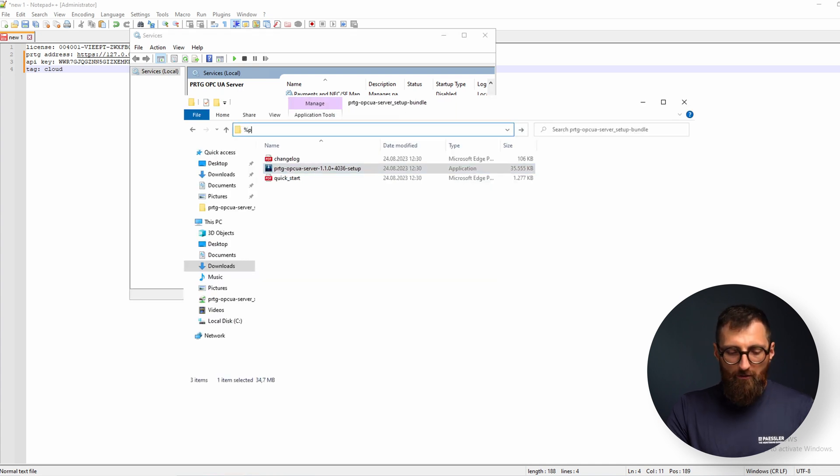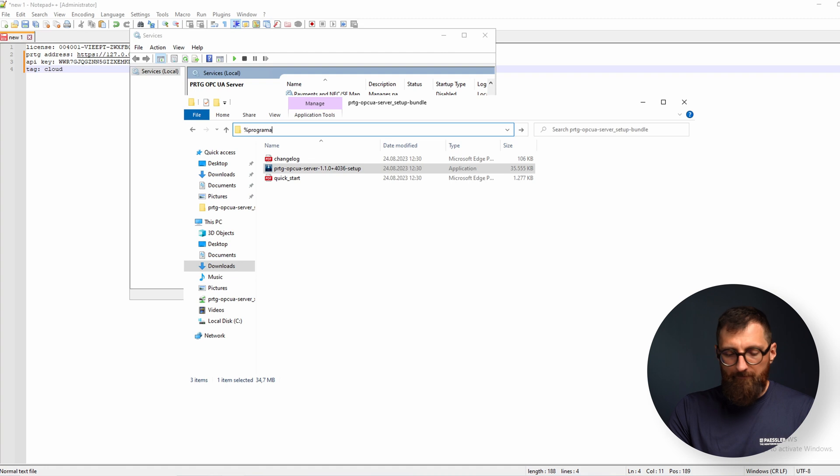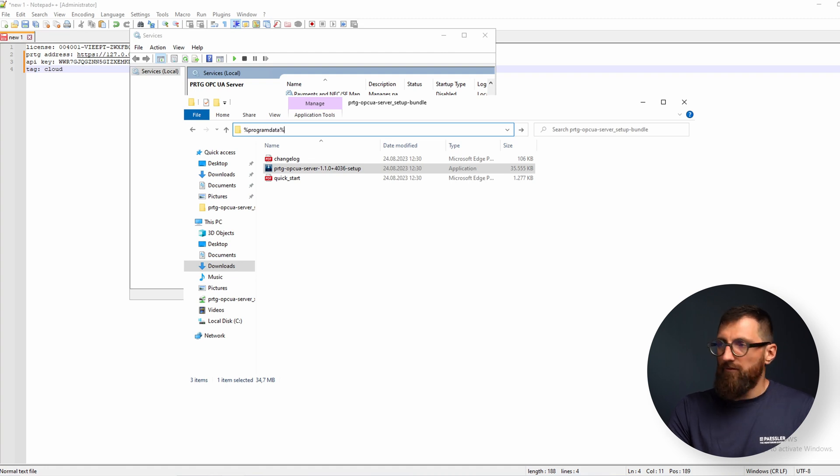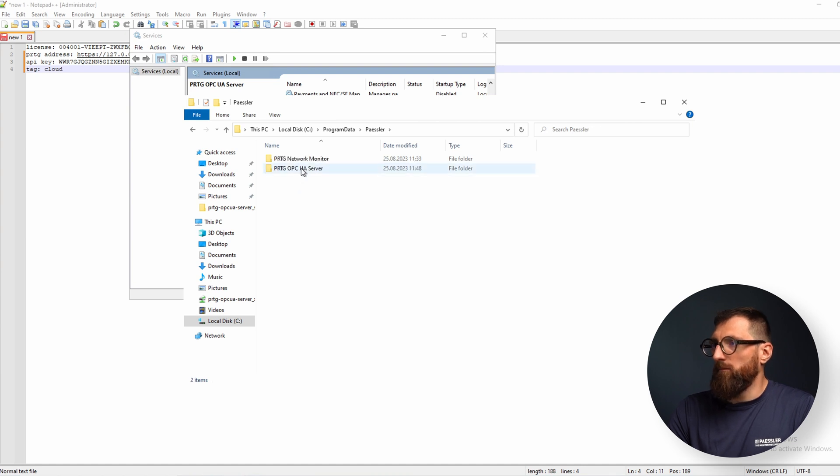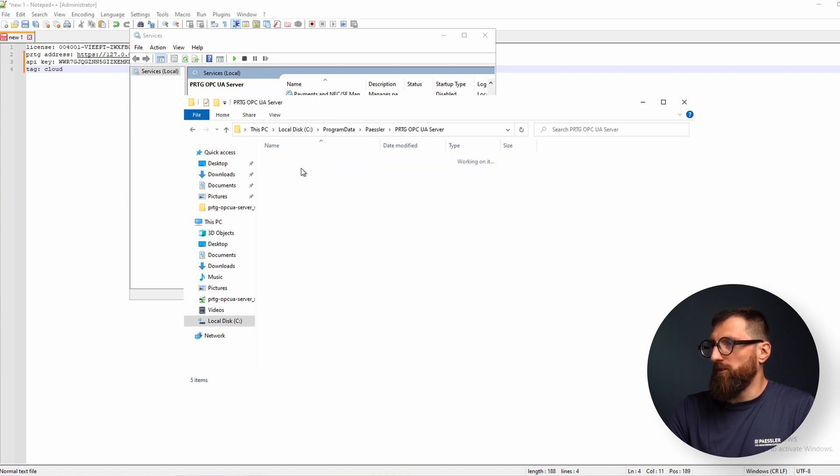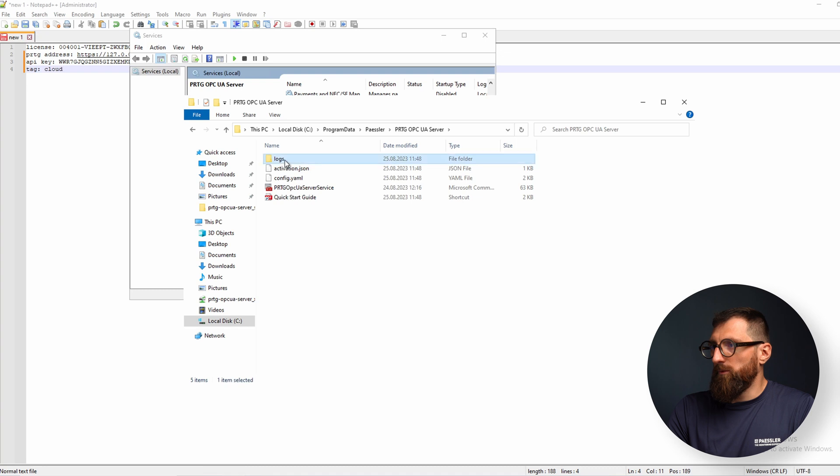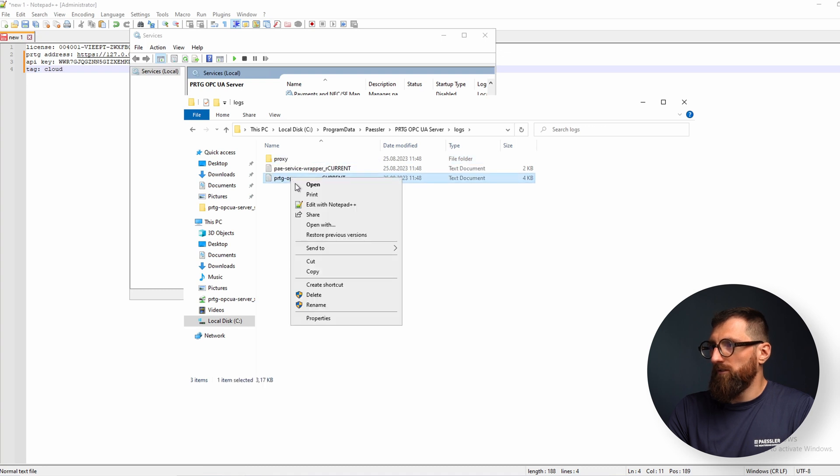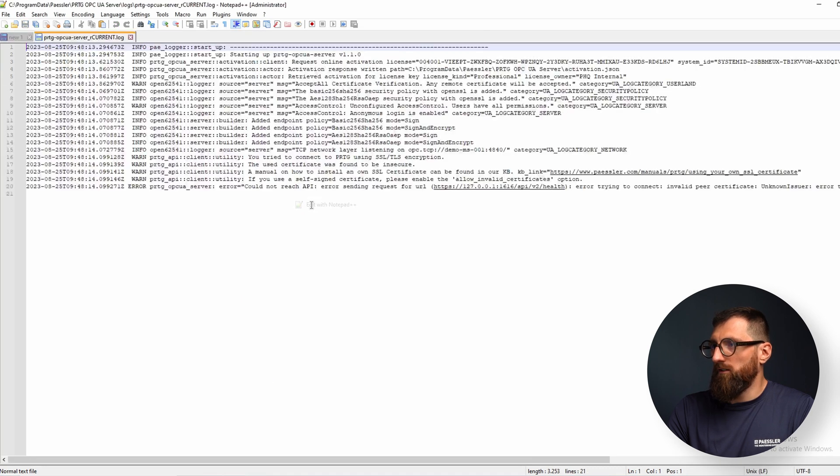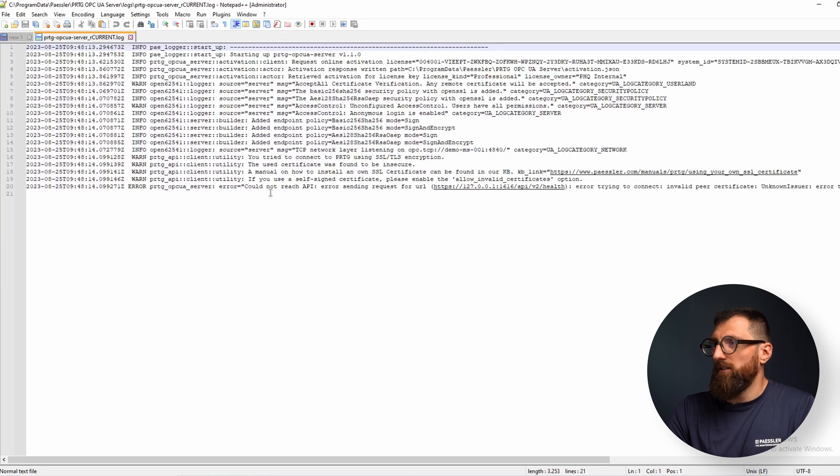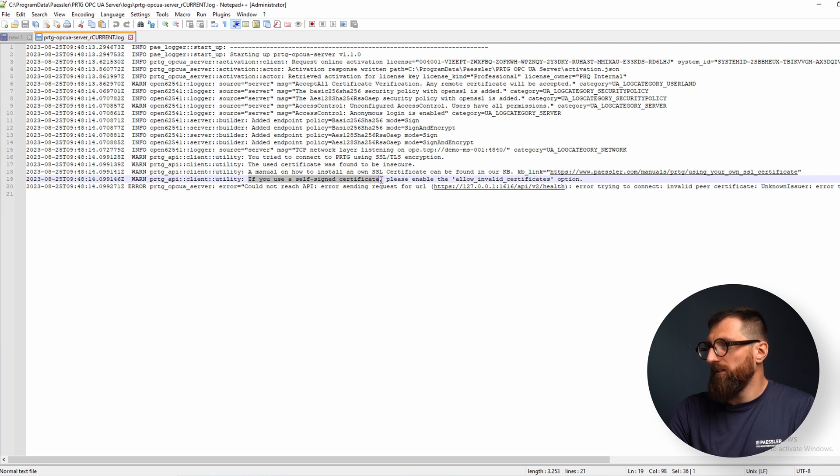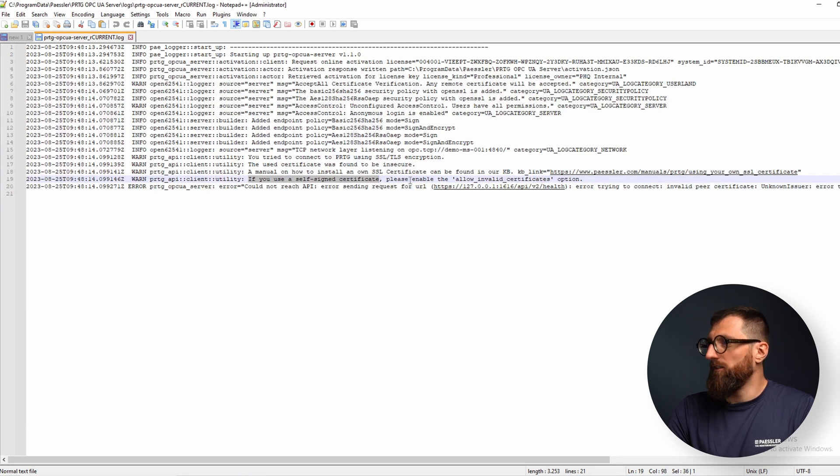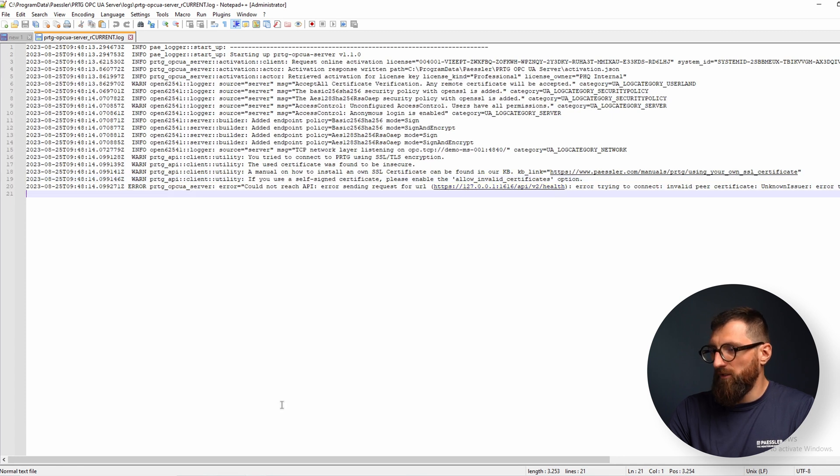Therefore we go to the program data where all the configuration is located for the Paessler PRTG OPC UA server. And first we have a look at the logs. Always look at the logs. Okay, it's already pointing us in the right direction. You can see if you use a self-signed certificate as I told you in the beginning, I'm using that for my installation. I have to enable the option allow invalid certificates. Okay let's do that.